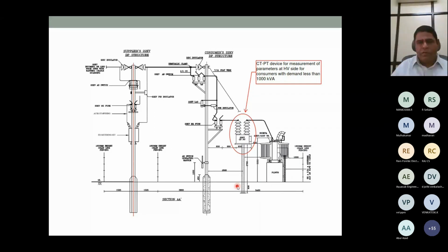So this is for consumers who have a connected load of 1000 kVA and below. Above 1000 kVA, they will naturally have a VCB in their circuit, and from the VCB they can take tappings from their CTPT and measure harmonics easily. I am telling this because there are several 11 and 22 kV consumers with below 1000 kVA load. If they want to measure for controlling these harmonics, they may have to install a CTPT like this, which will cost about 1.5 lakhs.